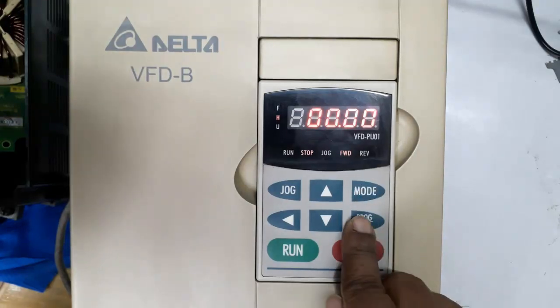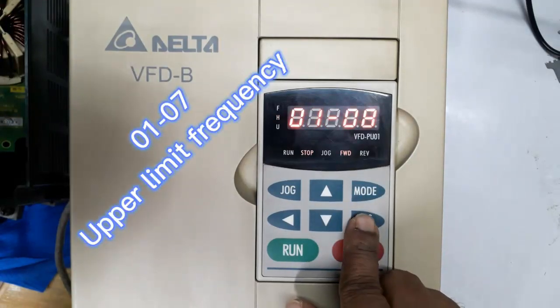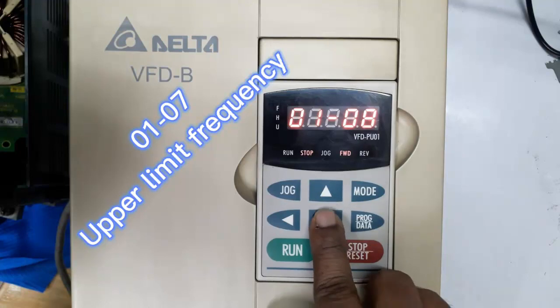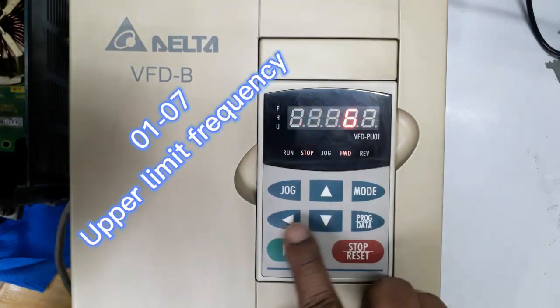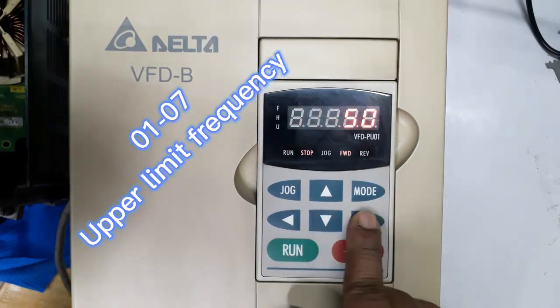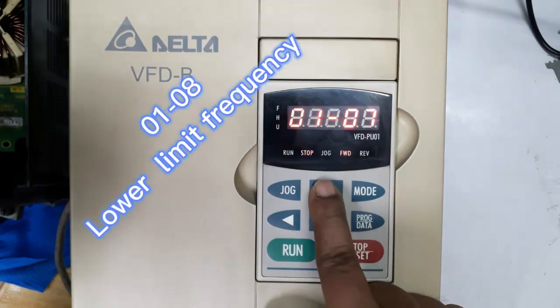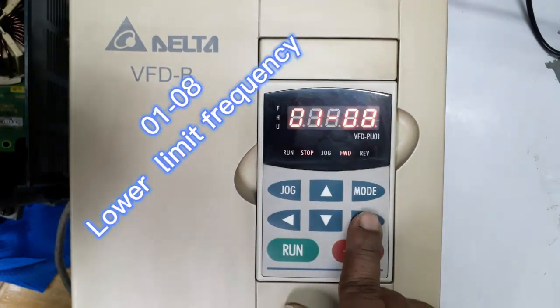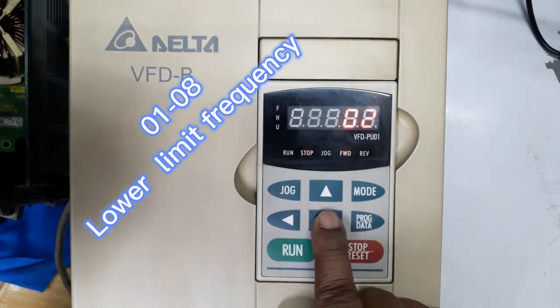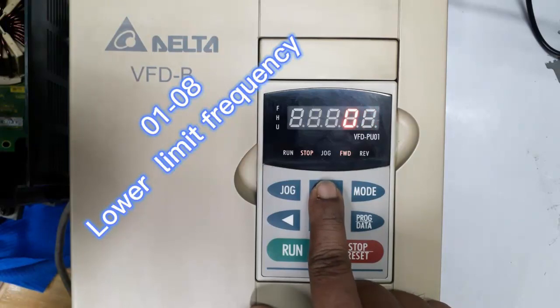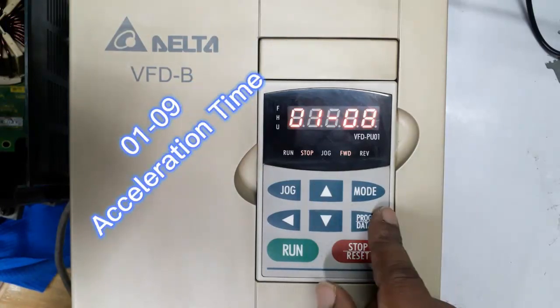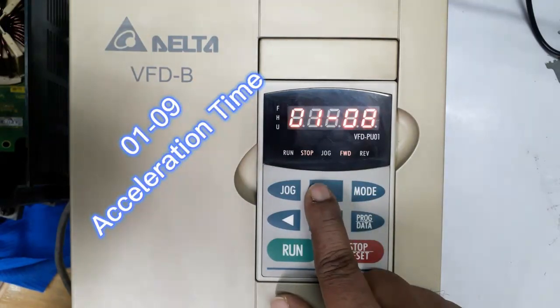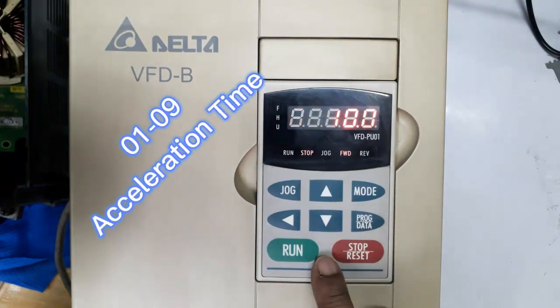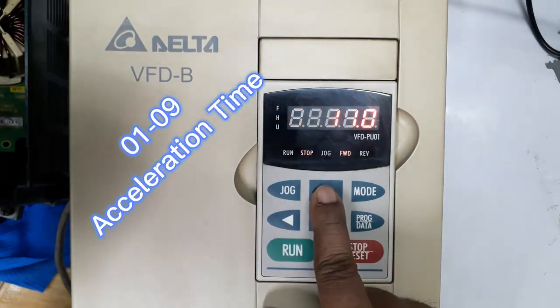How to set frequency limit in Delta VFD-B drive. For upper limit frequency, you set parameter 1-07, and for lower limit, 1-08. Those two parameters are for limiting frequency, and the acceleration parameter is for acceleration time, 1-09.